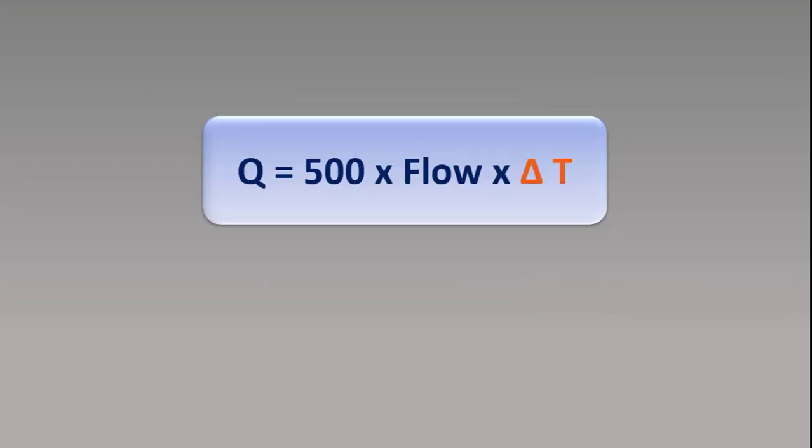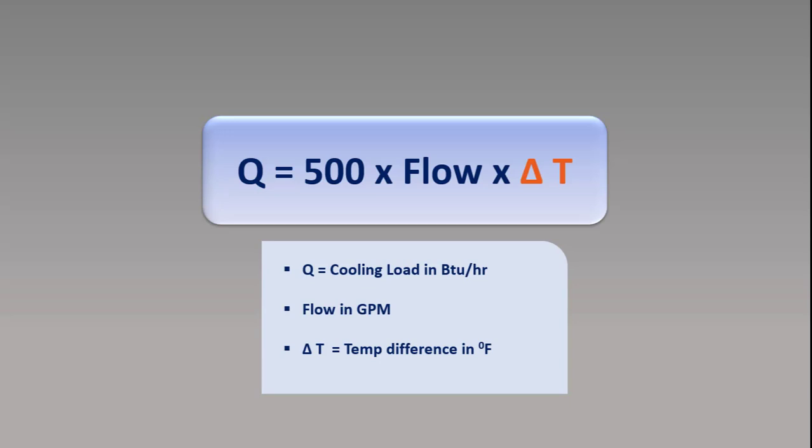Before discussing the constant flow primary chilled water system, let's briefly look at the load formula for cooling load. Here Q is the cooling load in BTU per hour, flow is the water flow in GPM, and delta T is the temperature difference between the supply and return temperature in Fahrenheit. In a constant flow chilled water system, flow is always constant, so the delta T will change with the change in the load.